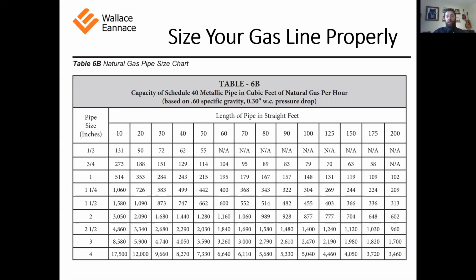You're going to starve that boiler of gas. You're going to have drastic drops once you start it up, especially when you consider multiple units. So this chart is basically just your BTU versus the length of your run, and that's how you're going to size your gas line. Please reach out to us anytime you have a job with any questions. We are always happy to go over the chart for you and answer these questions, and better earlier than later.